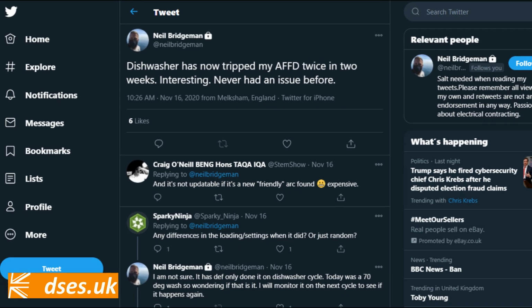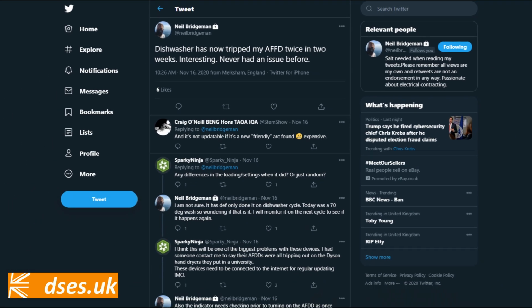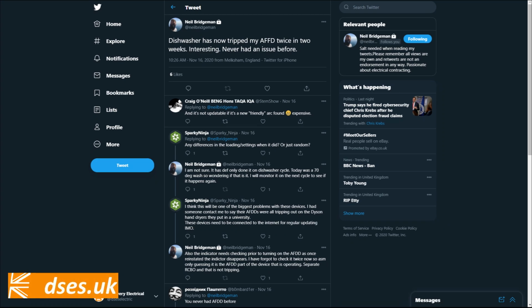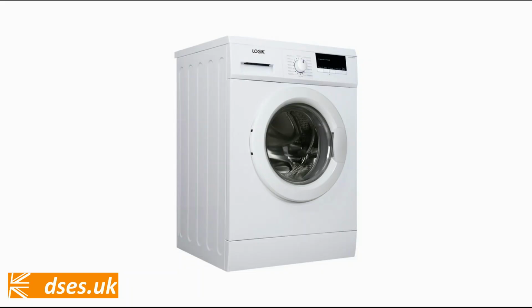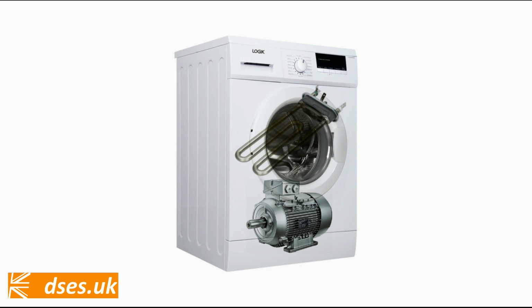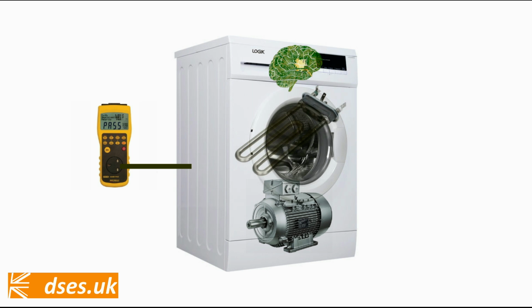Recently, Neil Bridgman was on Twitter scratching his head over a perceived AFDD trip with the use of his dishwasher, and this is where hidden problems may lie. For those who saw my PAT testing video, you may recall my washing machine example where a motor and heating element are present and a fault on either could cause nuisance tripping, of an RCD or AFDD as it happens. The problem is, even if you hook up a portable appliance tester, these components are on the wrong side of a PCB and simply aren't connected when the appliance is not powered, so it can pass a test despite having a fault. Only at a certain point in the operational cycle do these components get switched in, and that's when your protective device will operate.